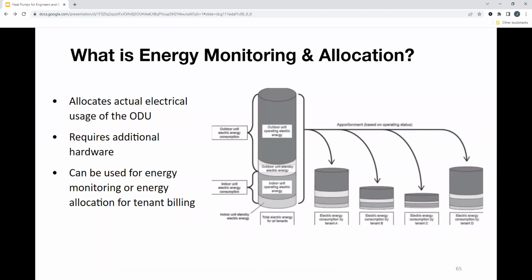All right, this is one of the big topics that I have today, which is what is energy monitoring and allocation? So most manufacturers do have a solution for energy monitoring. And what it does is basically, in simple terms, allocates actual electrical usage of the outdoor unit, right? So the outdoor unit has a certain kilowatts that it uses per month, right? Whether it's running in standby, and then also has a small indoor unit operating electrical energy. So all this is compiled together, and then it allocates based on internal system and other components that I'm about to talk about to different, in this case, tenants, right? A, B, C, D, and it'll give you an exact kilowatt usage.